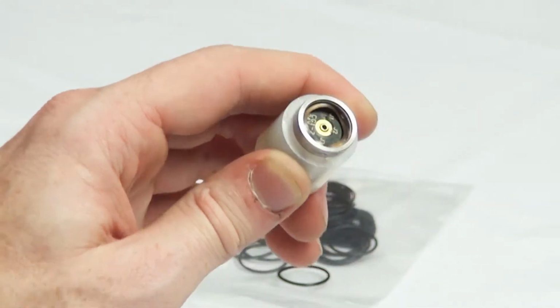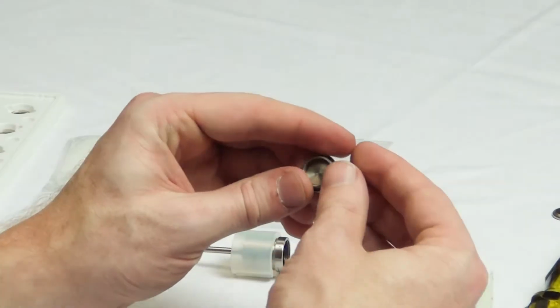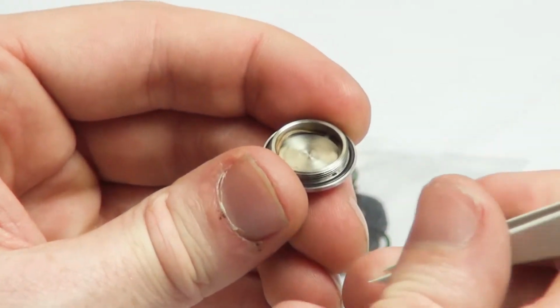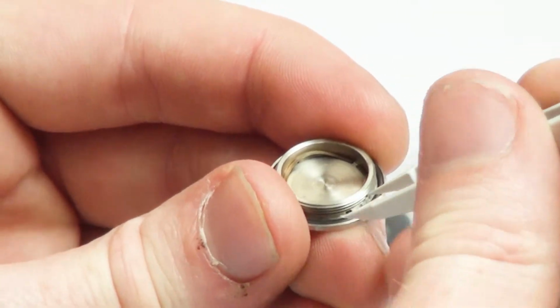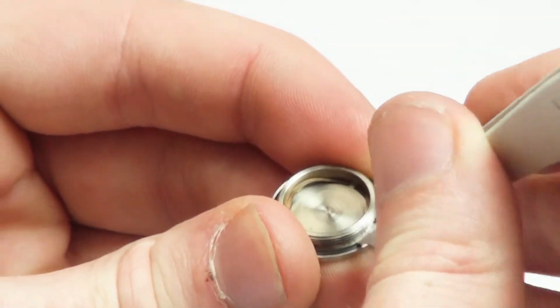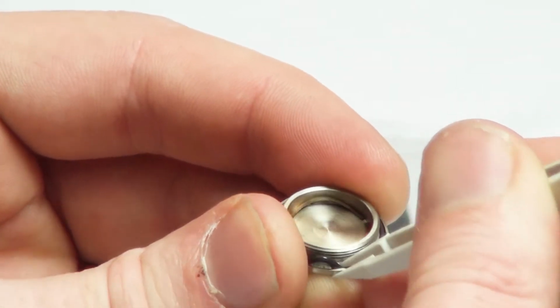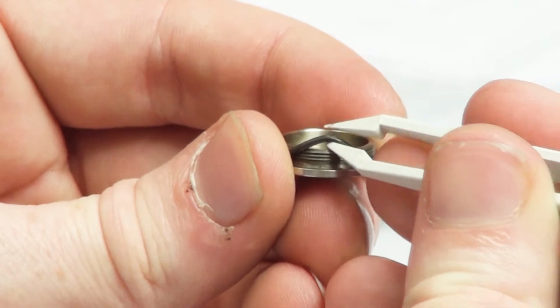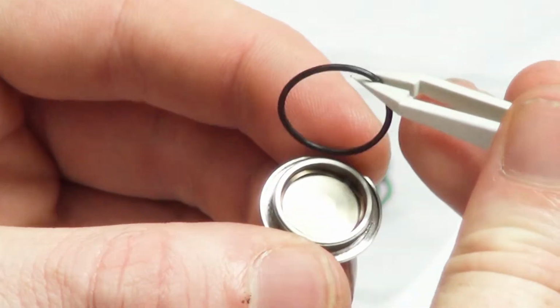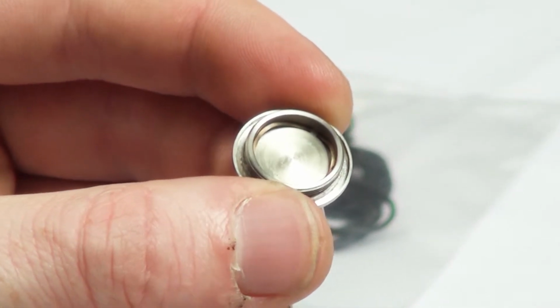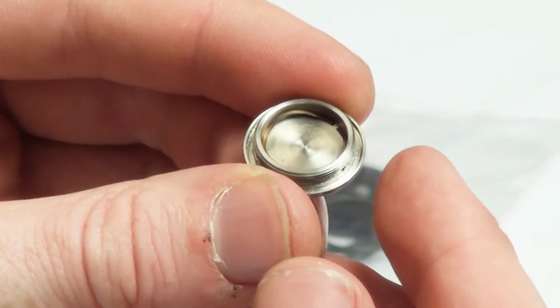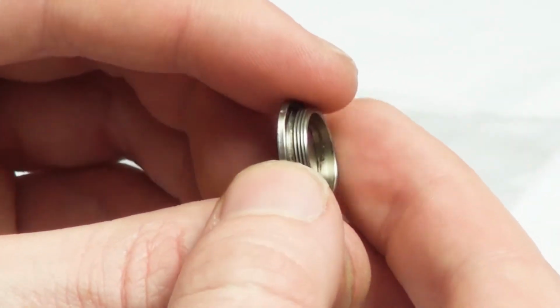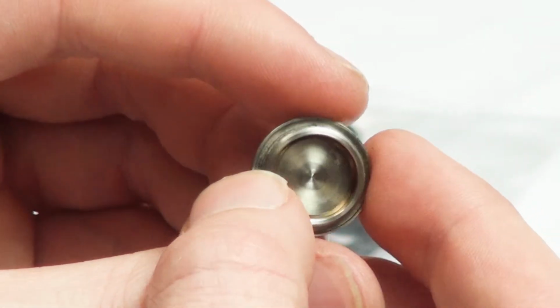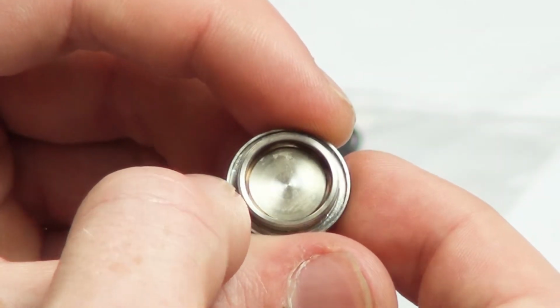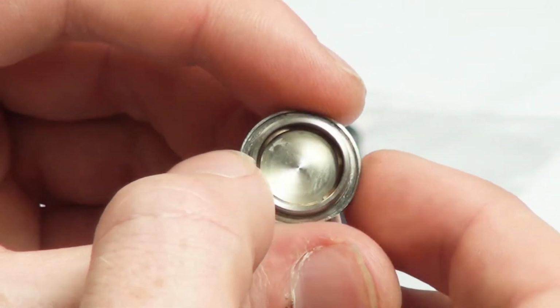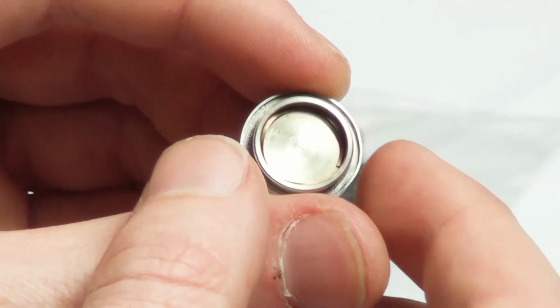Finally, remove and discard the O-ring, so I'll set the logger to the side. Remove and discard the O-ring to be replaced using the pick tool provided. Check for any scratches or nicks in the metal before reassembly. Make sure that if there are any in the sealing surfaces, or if there's contamination, that you return the logger to an authorized servicer for repair.